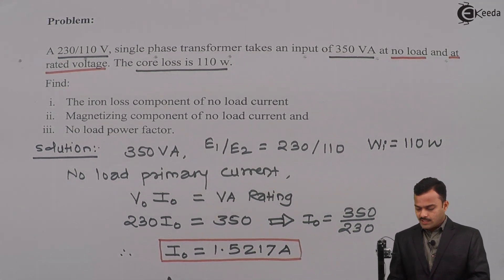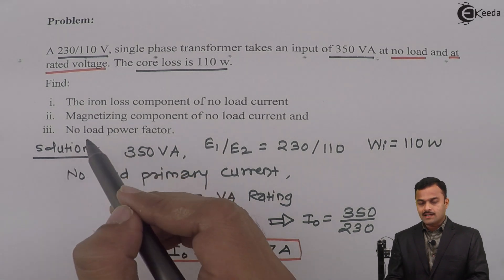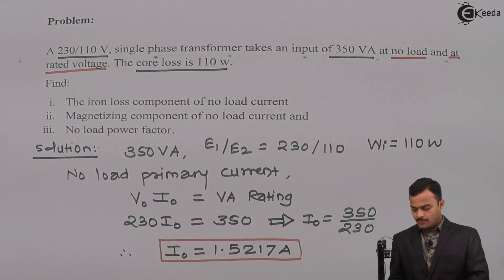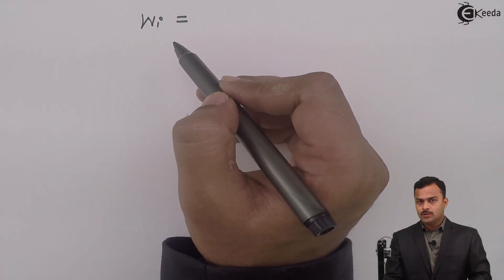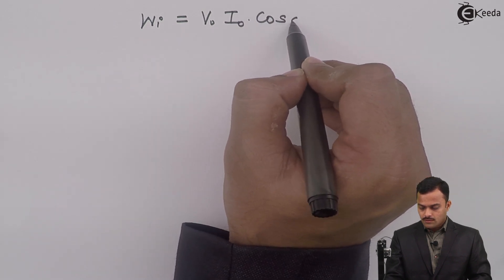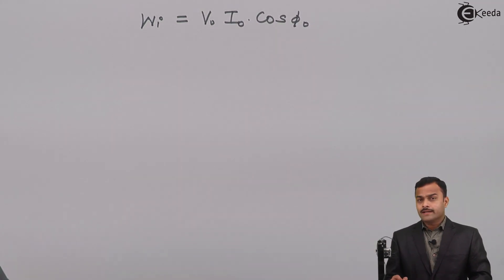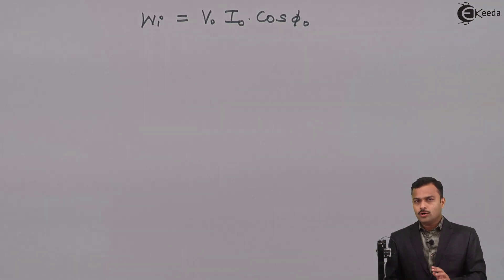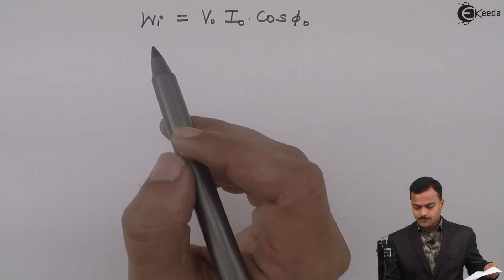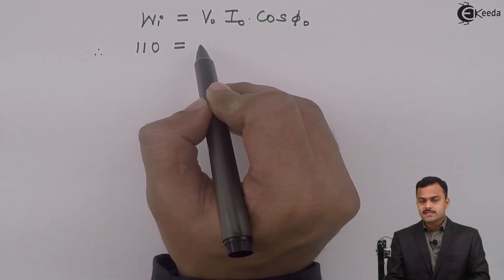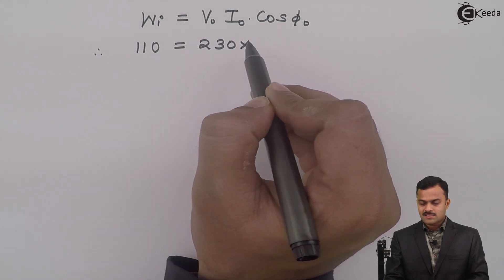A very important finding. How we are going to use this I₀ to calculate whatever the terms we are supposed to find out? So we know for open circuit test, core loss W_i is given as V₀ I₀ cos φ₀, where cos φ₀ is nothing but no load power factor - that is what we are supposed to calculate also.